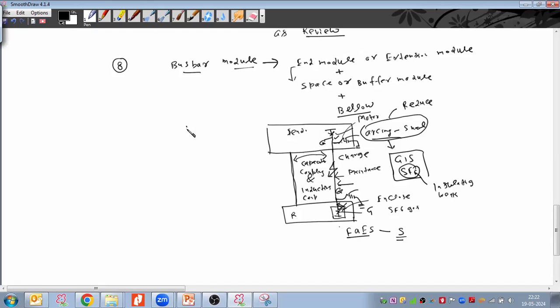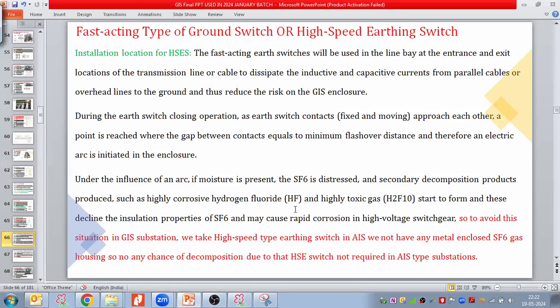And when it comes to the AIS, you know in the AIS there is no insulating gas present. We are not using any kind of gas, so the arcing is not going to weaken the insulating property of the surrounding air. We just need the contact of the earthing switch to be capable of carrying the induced current. Right? Am I making sense? Why do we take the high-speed earthing switch in the GIS and not in the AIS? The fast acting earthing switch will be used in the line bay to dissipate the inductive and capacitive current from the parallel cables or the line to the ground, and thus reduce the risk on the GIS enclosure.